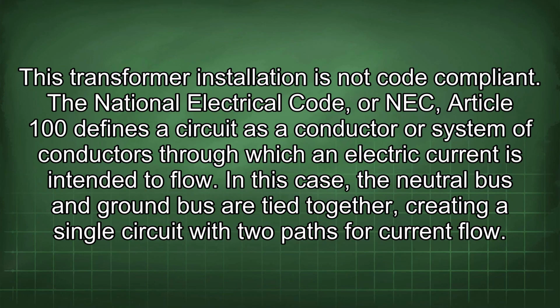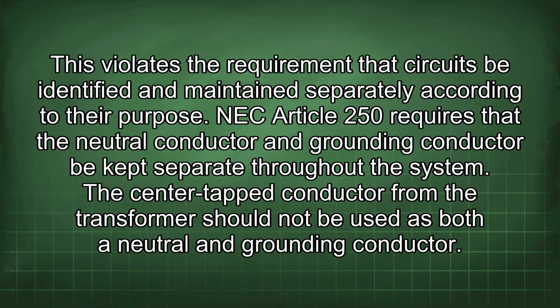This transformer installation is not code compliant. The National Electrical Code, or NEC, Article 100 defines a circuit as a conductor or system of conductors through which an electric current is intended to flow. In this case, the neutral bus and ground bus are tied together, creating a single circuit with two paths for current flow. This violates the requirement that circuits be identified and maintained separately according to their purpose.